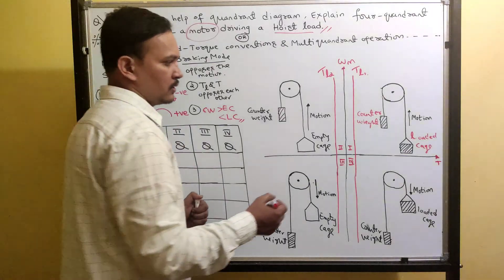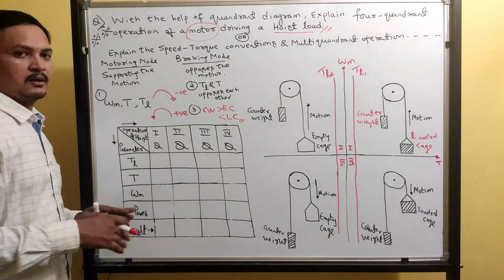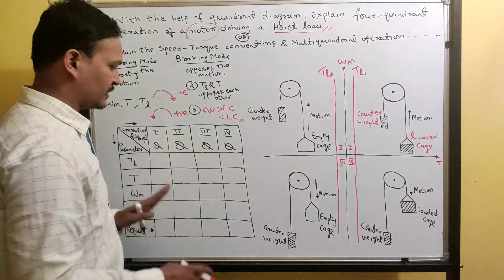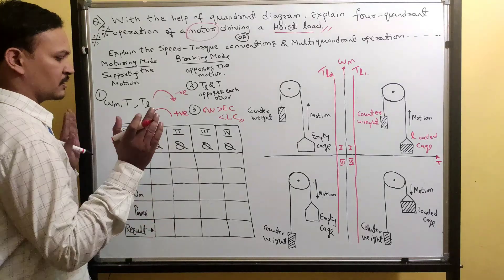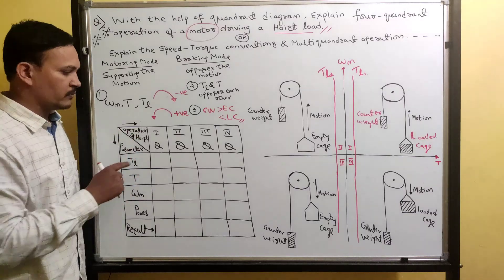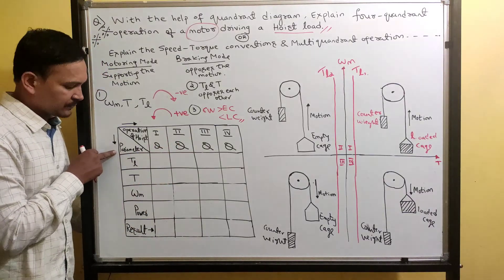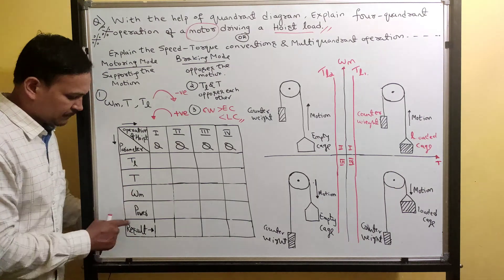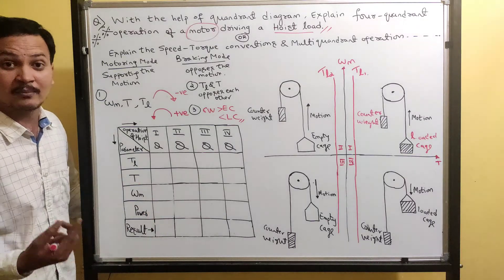In the first quadrant, the motion is upward — the loaded cage moves from bottom to top. The speed direction assists this motion. Since counterweight is less than loaded cage, motor torque is required to support this motion. Motor torque is in the same direction as speed. Load torque is opposite to motor torque. Load torque TL is clockwise, so negative. Motor torque is anti-clockwise, so positive. Speed is anti-clockwise, so positive. Power equals torque times omega: positive times positive is positive. Positive power means motoring mode — specifically, forward motoring.